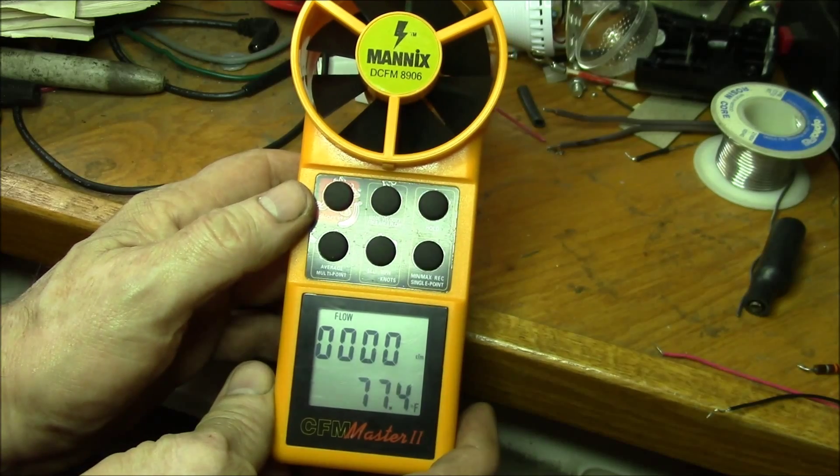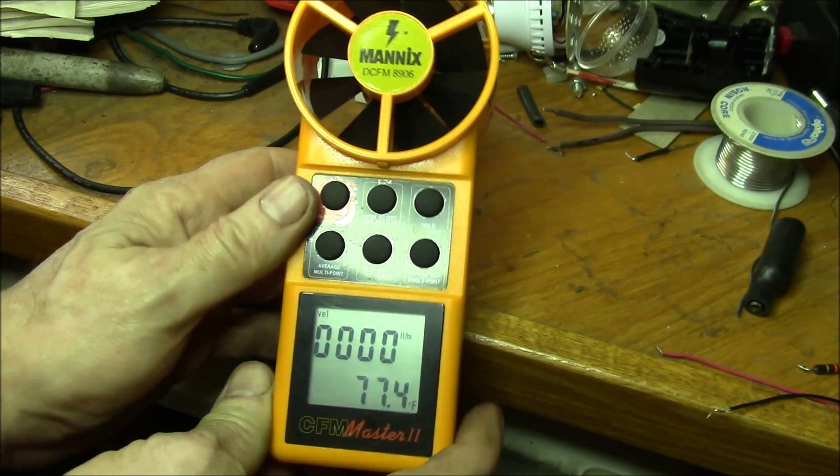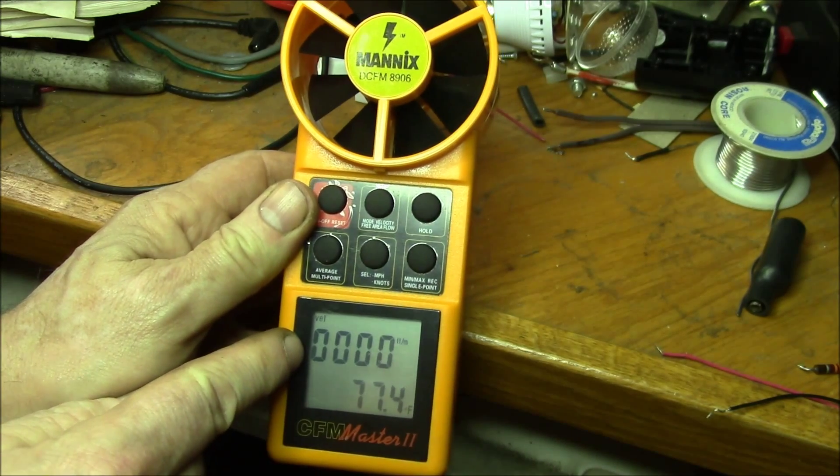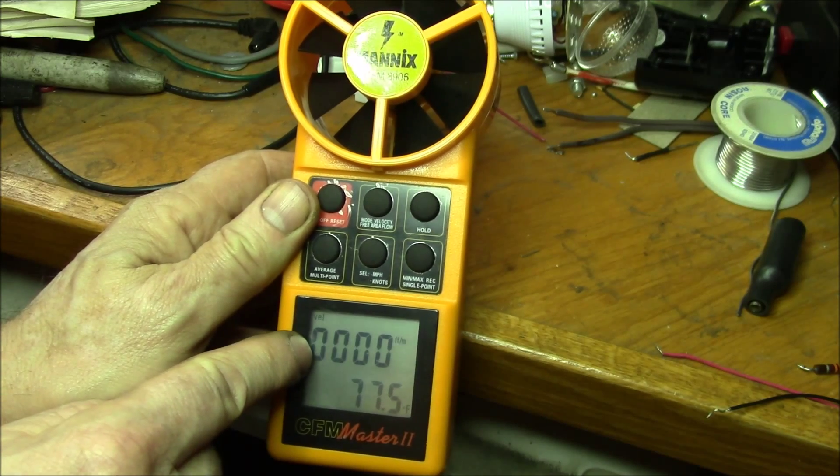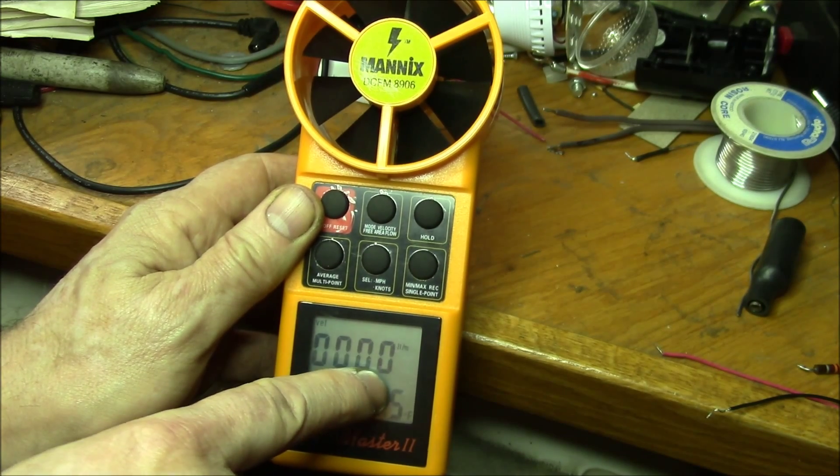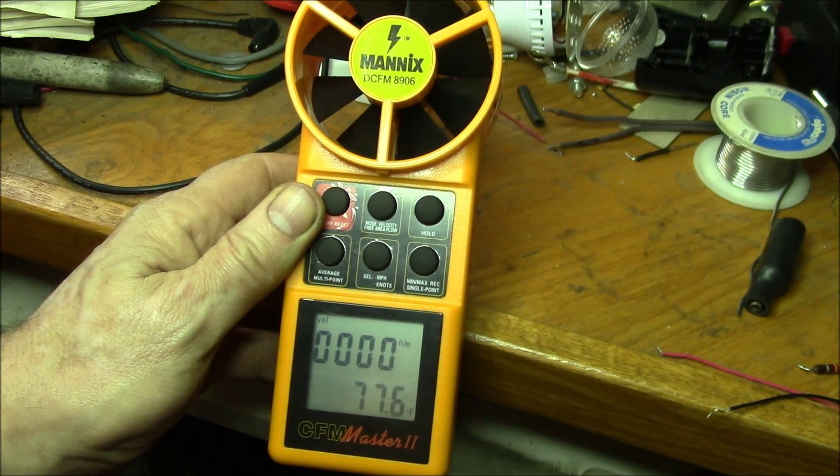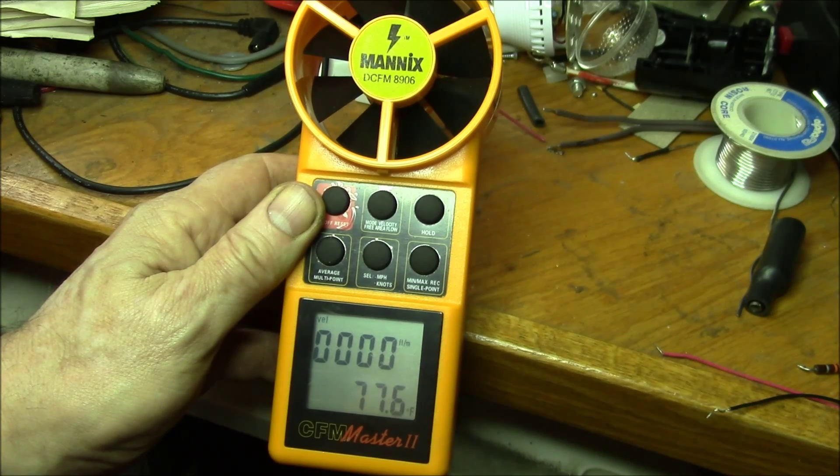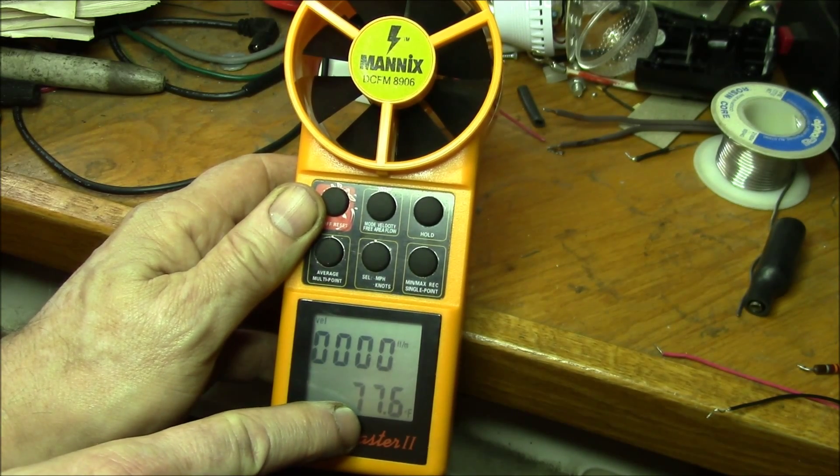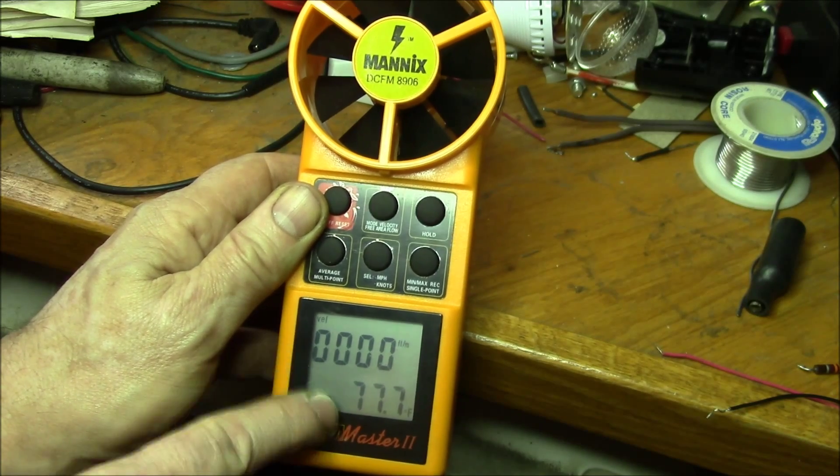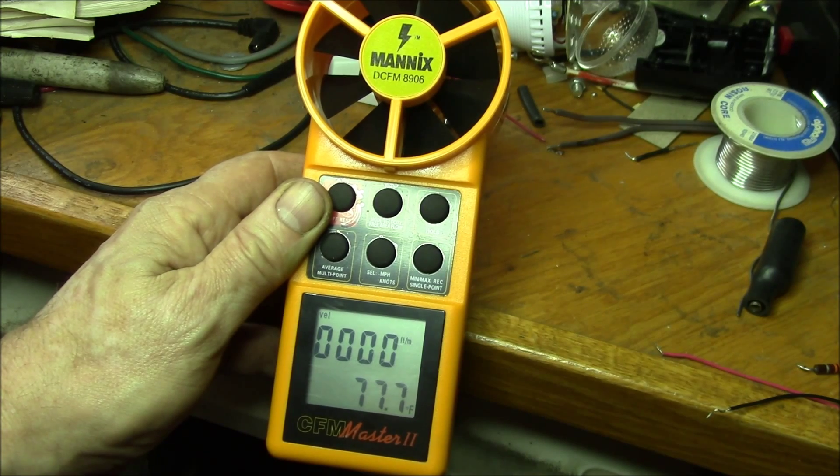So it's a little cumbersome. I actually usually don't bother with the cubic feet per minute because it's just a number you multiply. Feet per minute times the cross section of the duct to get your cubic feet per minute. It's just off by a factor, so I just generally use feet per minute and then get my temperature rise. That gives you a number that is proportional to the BTUs per hour.